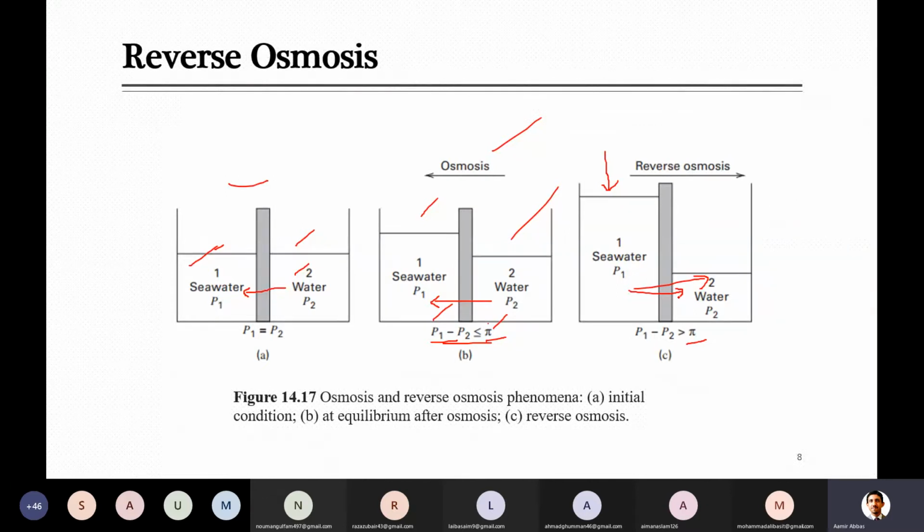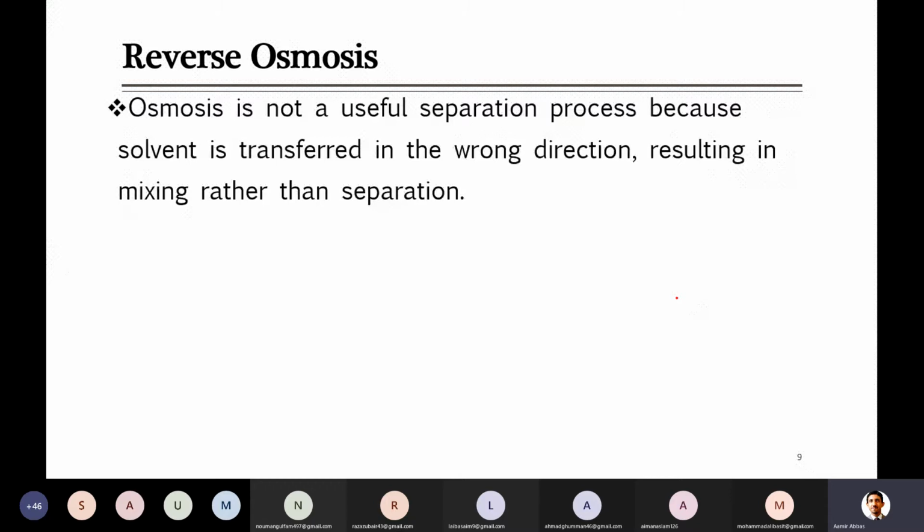Somehow, I think later there may be a figure about this, because we have some examples of reverse osmosis plants running worldwide, and their capacities are mentioned. Their pressure is usually 30 to 50 bar. That is quite high pressure when you are pushing the liquid through these membranes, especially for the cleaning of seawater. You need a huge 30 to 50 bar.